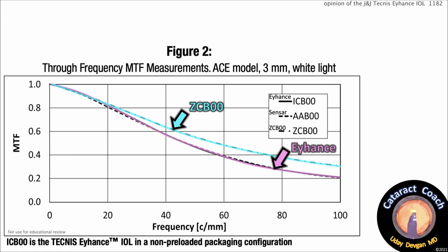Here are the through-frequency MTF measurements for different spatial frequencies — same eye model, 3mm pupil, white light. You can see there is a slight difference: the ZCB00 does perform better at different frequencies compared to the Eyehance. So for ultimate image quality at the desired focal point of far distance or plano, the ZCB00 is going to win.